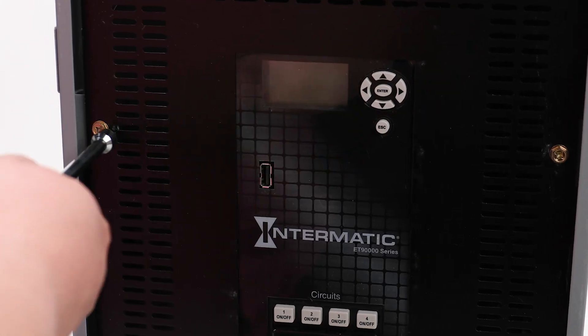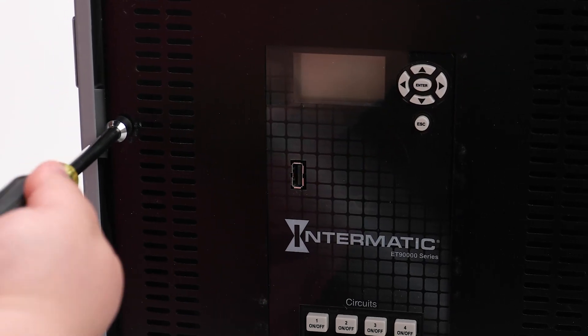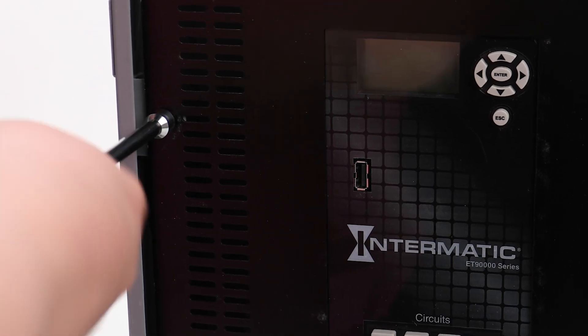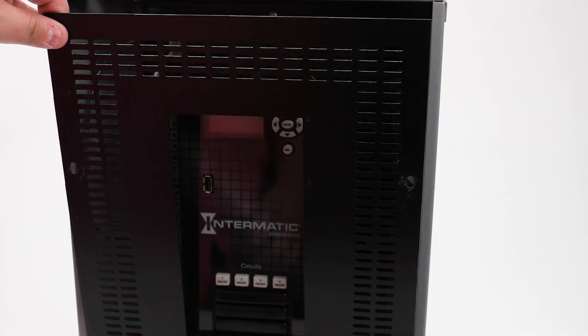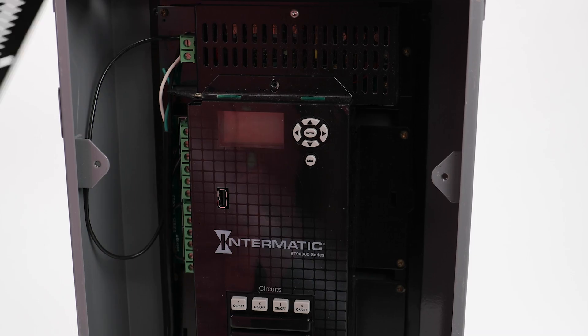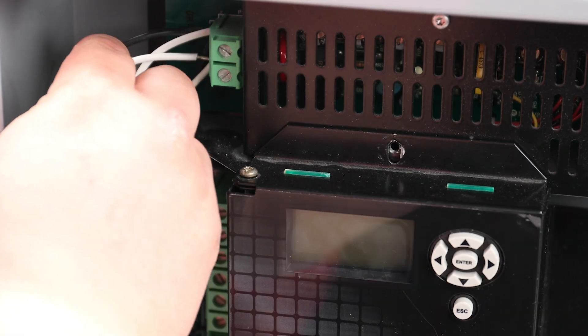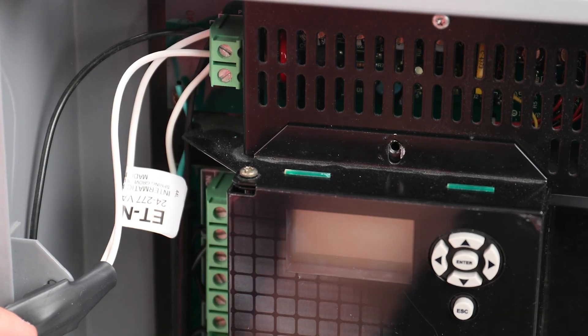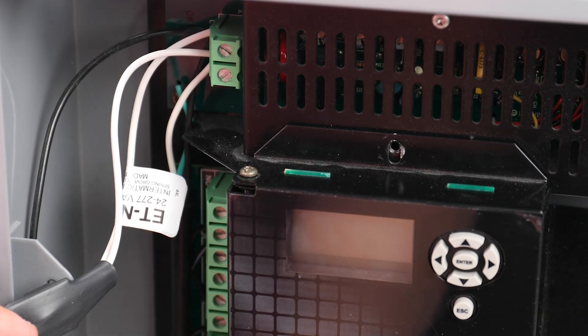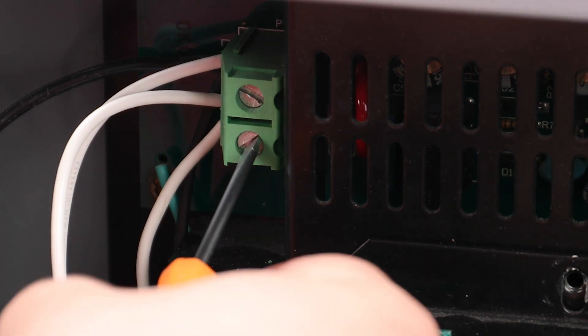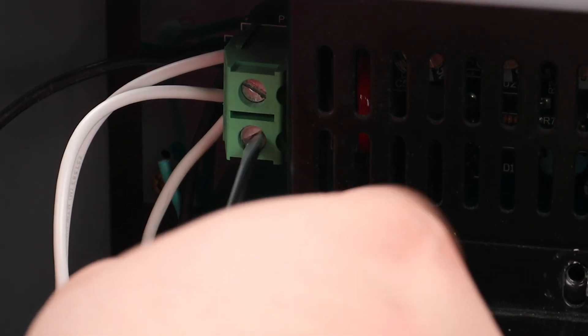If you are still experiencing issues from interference, you can install an additional filter parallel to the power input of the device being protected. In this example, we're placing the filter across the line input of the Intermatic ET-90,000 electronic timer.